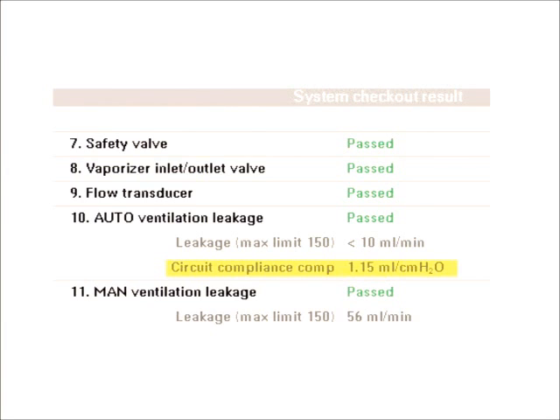Now, from this picture, this is an example of a system checkout. And if we look down here during the leak test, it also checked for my circuit compliance. So the circuit was occluded and it figured out my circuit compliance there. And as you notice, it's highlighted my circuit compliance is 1.15 milliliters per centimeter of water. And this is a very stiff circuit that is being used here. A normal circuit compliance is anywhere from 2 to 3 milliliters per centimeter of water.